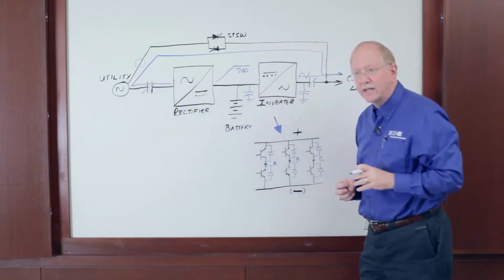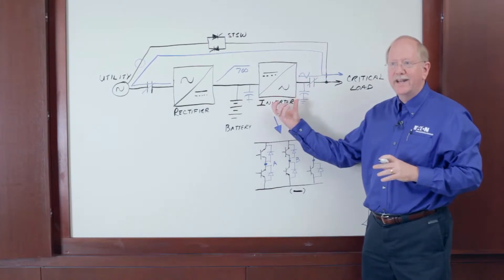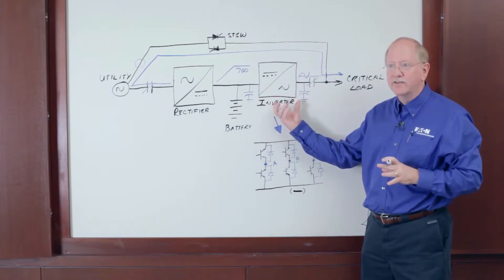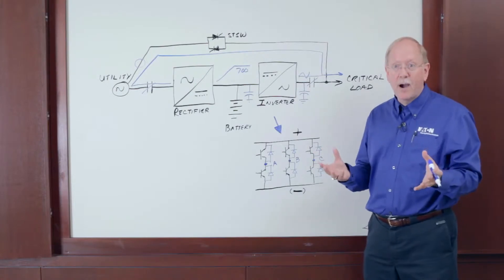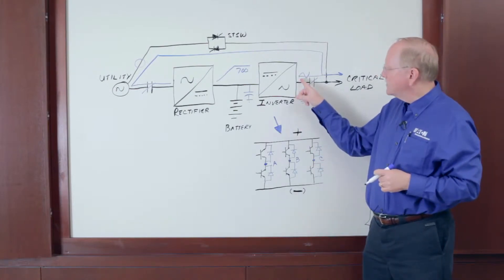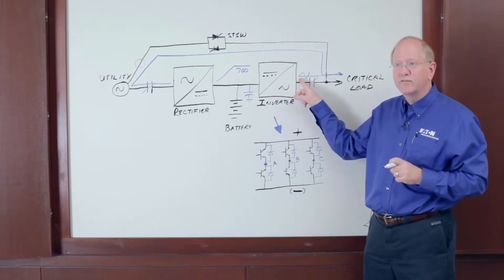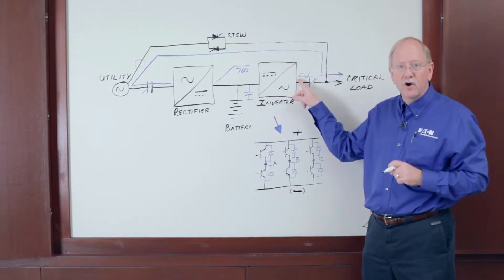The rectifier and inverter are suspended, but the inverter is still generating its gate commands for its main power transistors. It's not actually firing those transistors, so it's not using any power. But the gate command signals are already in sync with the output here, so I don't have to wait for sync when I flash the inverter on.